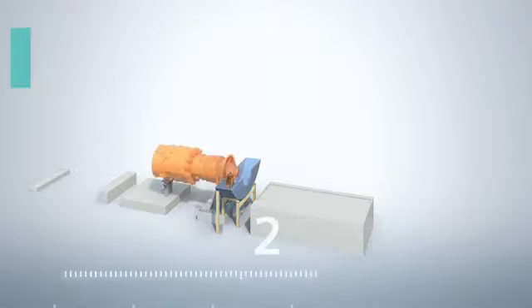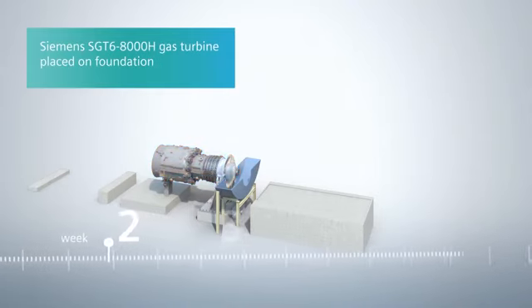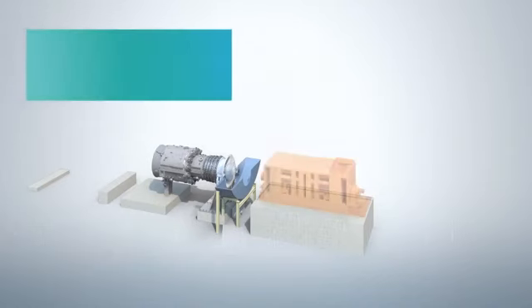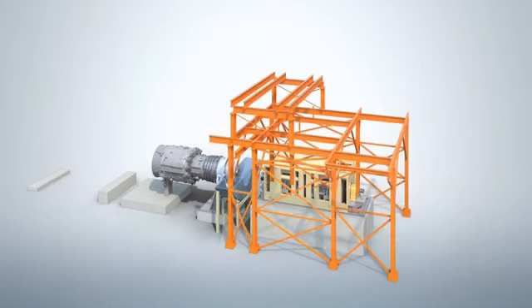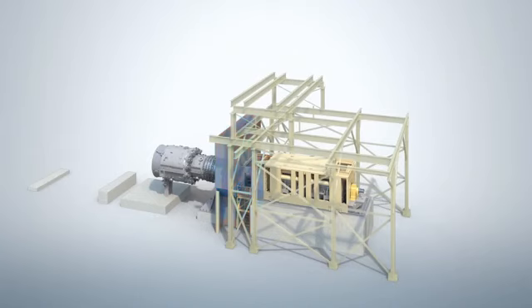In week two, the core components are installed, starting with the Siemens gas turbine, which arrives on site fully assembled. This is followed by the installation of the Siemens modular air-cooled generator. After the generator is installed, the support structure is erected around it. The generator housing and the intermediate shaft, which connects the gas turbine to the generator, are installed too.